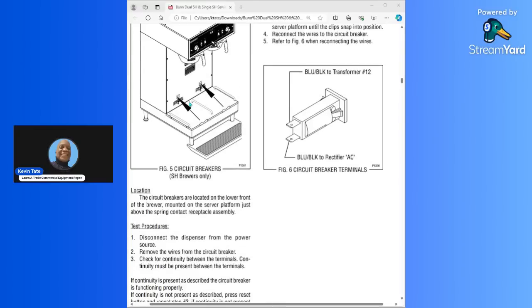So these are resettable circuit breakers right up here. When you remove those wires, you'd have to disconnect those wires from the back side. So you have to remove these 6 screws, just in case you weren't aware of it. And then you would have to open up that panel. That panel will slide out for you so that you can get access to the wires here. You'll remove these wires, and then they want you to test across the terminals.